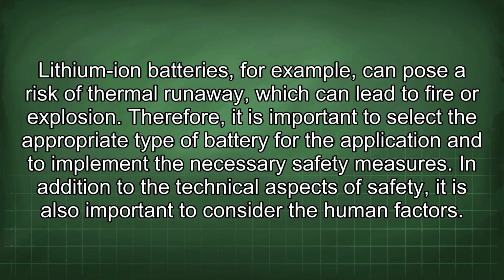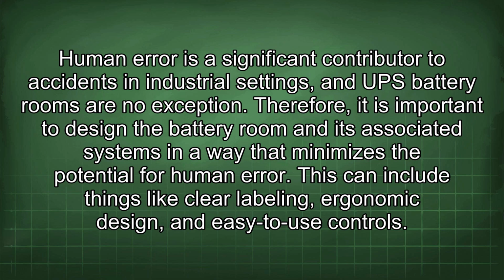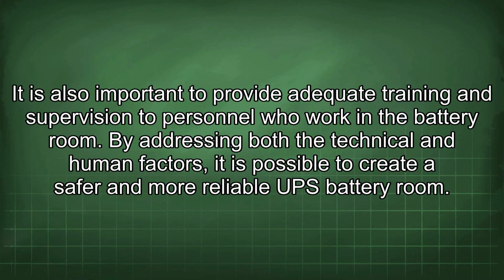In addition to the technical aspects of safety, it is also important to consider the human factors. Human error is a significant contributor to accidents in industrial settings, and UPS battery rooms are no exception. Therefore, it is important to design the battery room and its associated systems in a way that minimizes the potential for human error. This can include things like clear labeling, ergonomic design, and easy-to-use controls. It is also important to provide adequate training and supervision to personnel who work in the battery room. By addressing both the technical and human factors, it is possible to create a safer and more reliable UPS battery room.